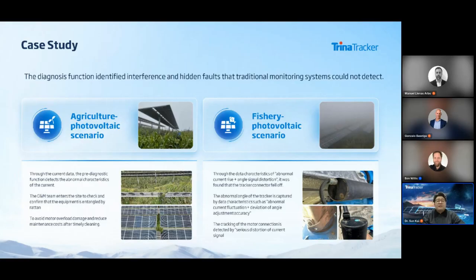The first is the agri-PV scenario. Motor current analysis revealed abnormal patterns, and a site inspection confirmed that vines had wrapped around the equipment. Cleaning the vines prevented motor overload and reduced maintenance needs. During crop growth periods, when field access is limited, pre-warnings help ensure timely action.